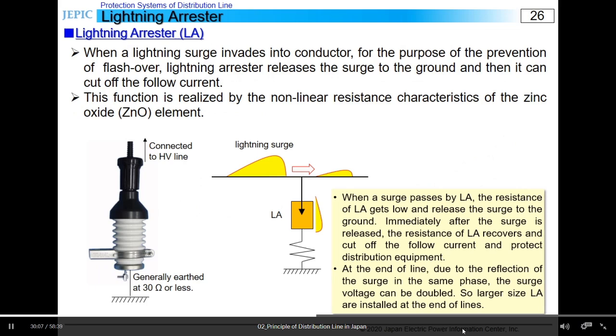This slide is about lightning arrestor. When a lightning surge invades into line conductors, lightning arresters can release the surge to the ground for the purpose of the prevention of flashover, and then it can cut off the follow current when the surge voltage reduces down to a certain value. In this way, lightning arrestor protects distribution equipment from being damaged. This function is realized by the nonlinear characteristics of zinc oxide elements inside the lightning arrestor.